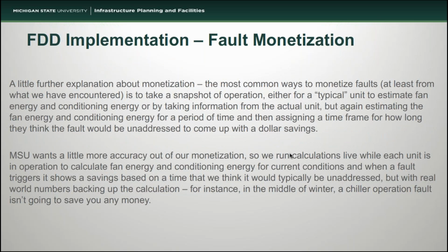So I wanted to add a little bit extra about fault monetization here. The most common type of monetization is that the company or the people providing the monetization take a snapshot of how typical units run, and they'll estimate the energy associated with conditioning that air and moving that air, or they may take information related to an actual unit, but again, they estimate the energy associated with it. They pick a period of time that they believe the fault would not be addressed for, and then they extrapolate that to a dollar amount, saying, okay, if this fault happens anytime during the year, then we're going to see this many dollars of impact.